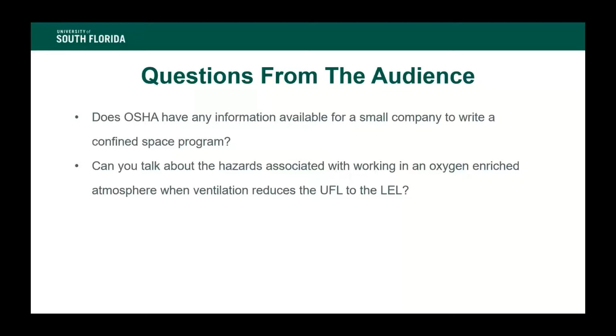Yeah, what happens is that when you do your air monitoring and you find that the LEL is over 10%, in most cases you're going to be using mechanical forced ventilation in order to bring the values back to what you want. And also, like we mentioned before, you have to pay attention to the oxygen concentration. Between the value of the oxygen and the LEL, you're going to determine that your atmosphere is safe to enter.